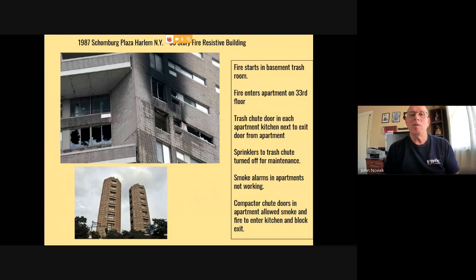But in this case, the fire starts in the basement trash room. Fire department responds to a report of a trash fire, something they get all the time. The issue was that in this building, each apartment had its own trash chute inside the kitchen, which is kind of rare, from what I've been told. The trash chutes are usually located out in the public hallway, so you would have to take your trash out into the hallway, go to a trash room or a trash chute, open the trash chute door and dump your trash in. In this case, the building was built with trash chutes in the kitchens. We don't know whether the trash chute door in the kitchen was ajar, didn't have a good seal, or wore out over time, but the compartmentation wasn't there.